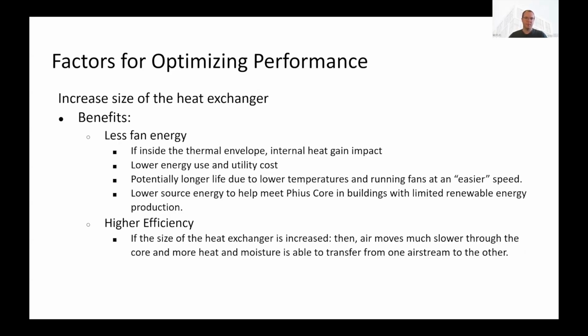Alternatively, we could keep the same airflow but increase the size of the heat exchanger. It has the same effect. Same airflow, bigger heat exchanger core, the air is going to move slower through it, and then there's going to be higher transfer rates from one airstream to the other.